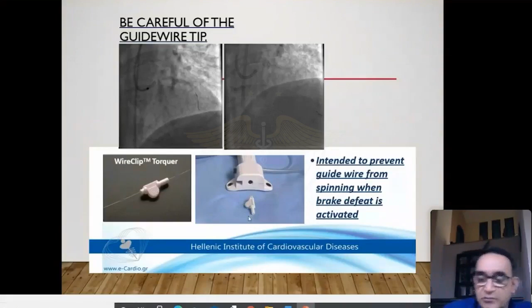But more than this, when you do what is called dynaglide, where you pass the rota burr inside through the guiding catheter, and it is not going easily, you have gone on a slightly higher speed from 0, let us say 50,000 or so, that is slow for a rotational atherectomy. Then if the brake is applied, how will this move forward? So you need to hold the wire and first defeat the brake. What we call brake defeat has to be activated. You can see here, there is a small black button on this that has to be pressed, so that the wire is still, and the rota burr is allowed to move on this wire. And you are afraid that once again it may rotate, therefore you need to hold this clip.